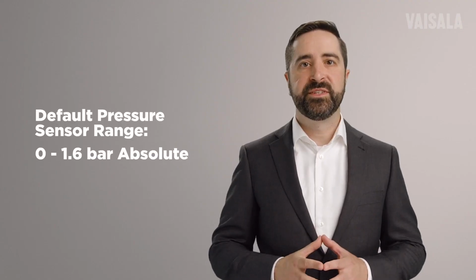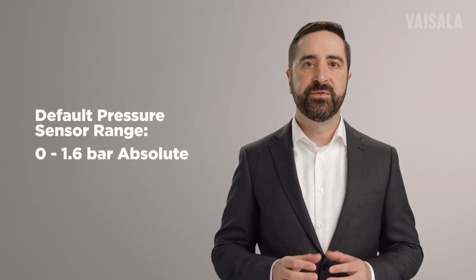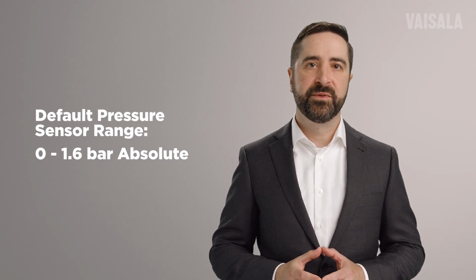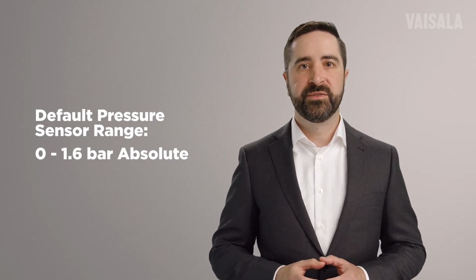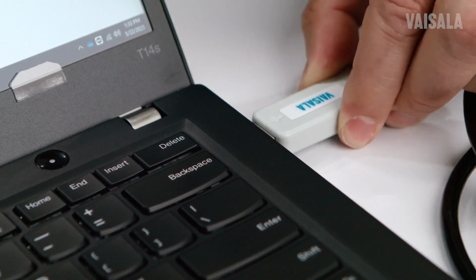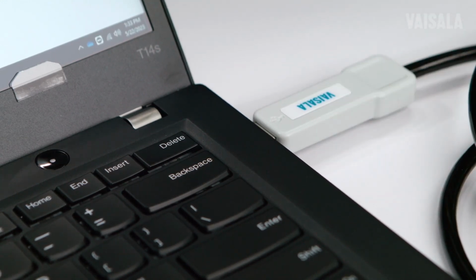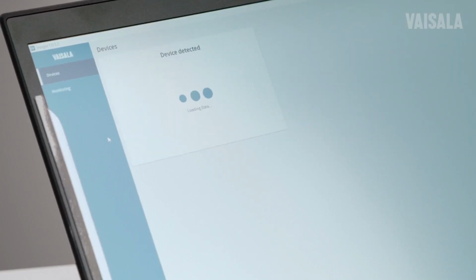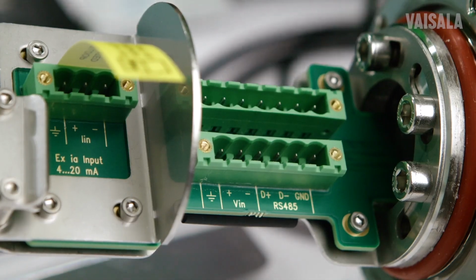Requirements for an external pressure sensor are that it be EX-rated for use in biogas applications and have an output in absolute pressure units. The default range for this sensor is set at the factory for 0 to 1.6 bar absolute, but other measurement ranges can be used as well. When using a sensor with a different range, for example 0 to 2.5 bar absolute, you can simply program that range into the probe using our USB service cable and Insight software, or with the available Modbus connection.